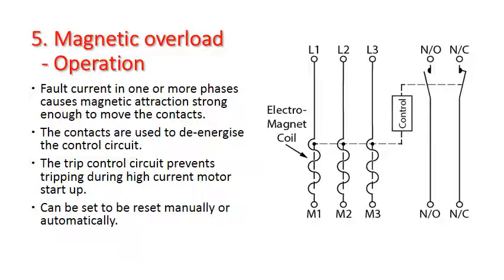The control circuit prevents tripping during startup, because we know that a motor draws high current, 6 to 9 times full load current, when it's starting up, and if we didn't deal with that, every time the motor started up, this would trip out. So we have to have an electronic control circuit to stop that and to time it until the motor is started. Once the overload has been tripped, it can be set to either manually be reset or automatically reset.